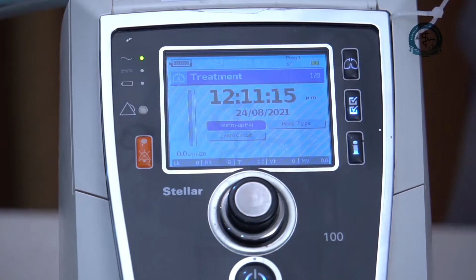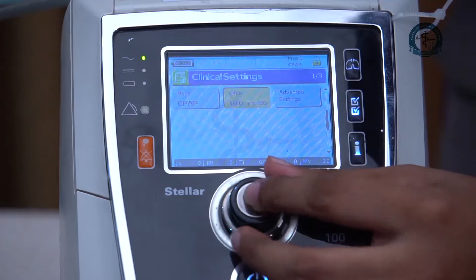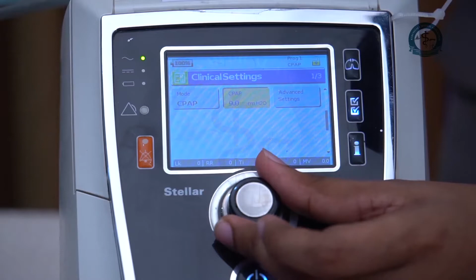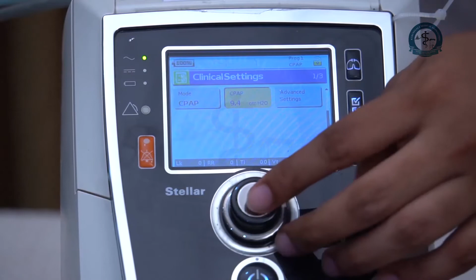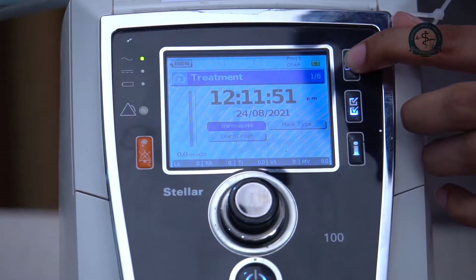Clinical setting screen. You can change the clinical settings here. In the clinical setting screen, there are 3 settings. Selecting the mode: CPAP, S, T or ST mode. Once you select the CPAP mode, you will be able to select pressure for CPAP. Generally, it will range from 5 to 20 depending on the patient's condition. If you select S, T or ST modes, you will be able to select IPAP and EPAP pressures. All selection is done by pressing the middle knob and value change is done by rotating the knob.